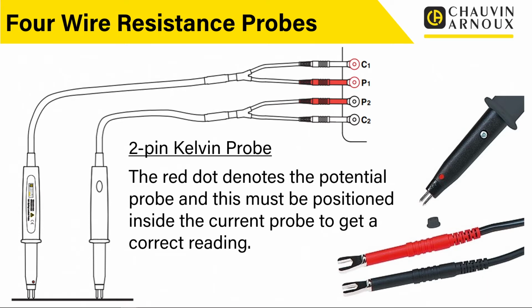So these are great if you want to make contacts onto some quite small items, where getting big chunky crocodile clips on, or certainly 2 or 4 sets of crocodile clips, is going to be difficult. So in this case, these probes are very good. We do offer a range of different types of probes that you can use, but in this case, just be aware that we do note where the potential and the current probes are and position them accordingly. So it's quite an interesting one. That one's something maybe that most people aren't aware of.